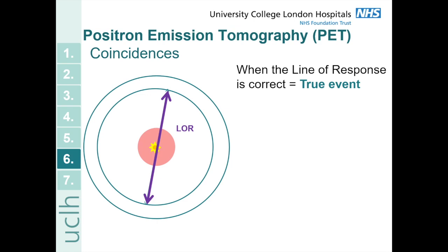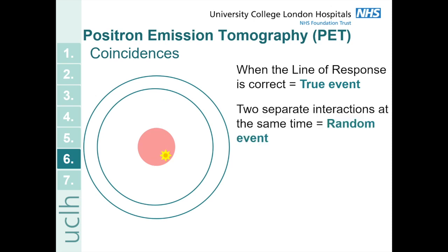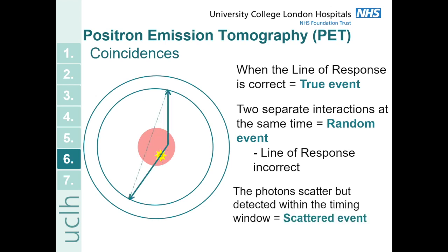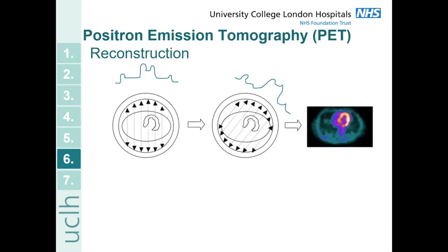When the line of response is correct — the event really did happen along that line — we call this a true event, and this is what we want to be detecting to build up our image. You could also have two separate interactions at the same time and record the photons from those two separate events, drawing an incorrect line of response between them — we call this a random event. You could also have a case where one of the photons scatters before being detected, again producing an incorrect line of response — this is called a scattered event. Image reconstruction in PET is very similar to that for SPECT: instead of having projections from different angles of the rotating head, you build up your projections from those lines of response, and then use them to create your 3D image through a reconstruction algorithm.